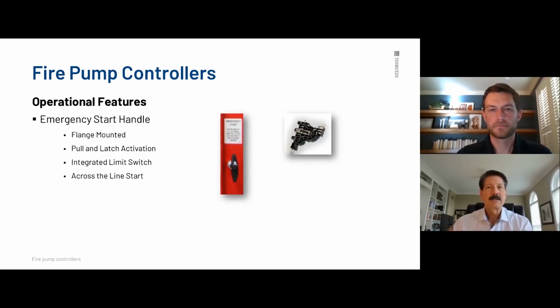And the arcing that could occur by trying to do that without the power off could do some damage to the contactor, could actually carry it through and maybe a surge or spike to the circuit breakers themselves. So the procedure again: turn the power off, pull your emergency start handle into the lock position, turn your power back on. That is the standard procedure, and we're not the only manufacturer that suggests that.